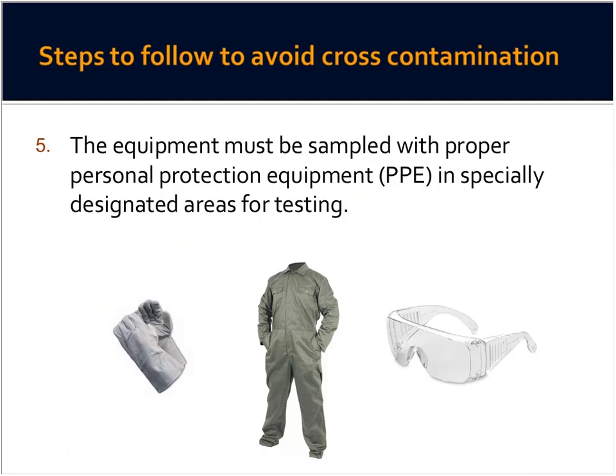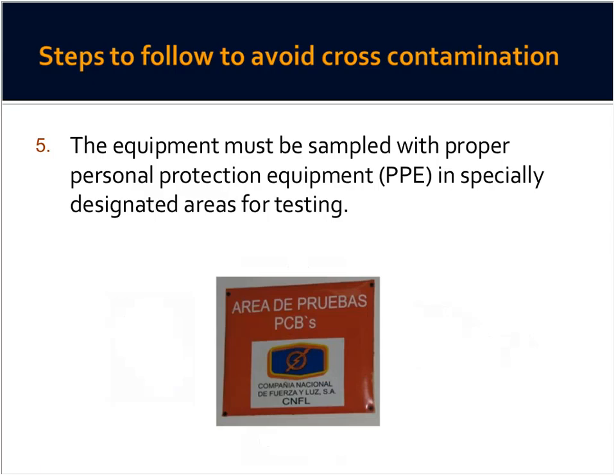Another step is to properly use personal protective equipment in specially designated areas for testing. We need to have goggles or glasses. We need to have gloves. In some instances, a Tyvek suit will be necessary, but if it's just for the sampling, it may not be necessary. The equipment must be sampled with the proper personal protection equipment and in specially designated areas that are isolated or in a specially marked off area within the maintenance workshop. Here we have a sign that says area for PCB testing.